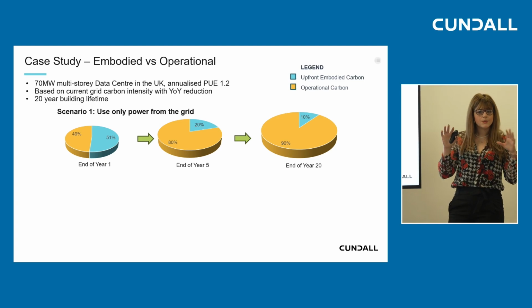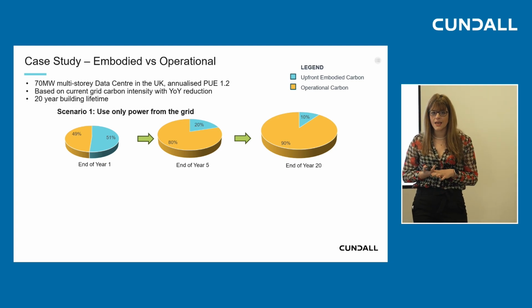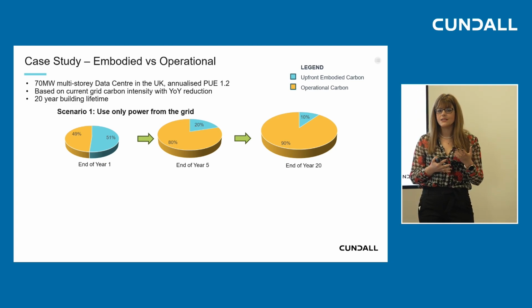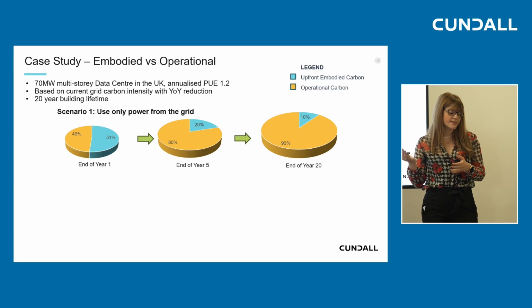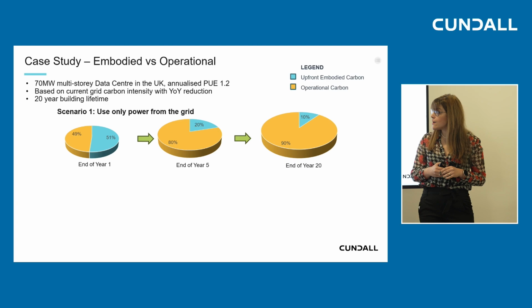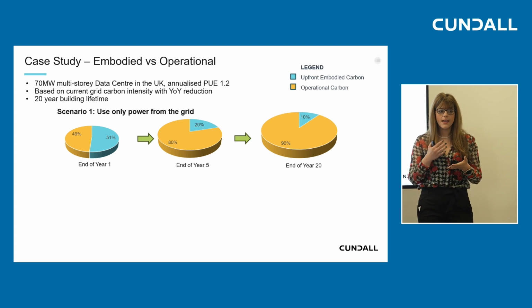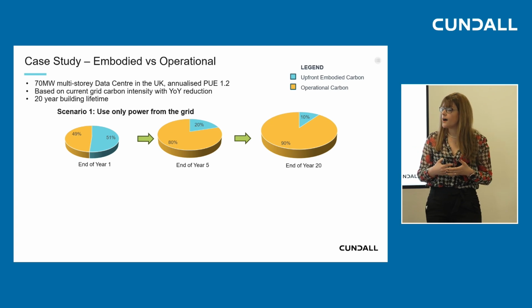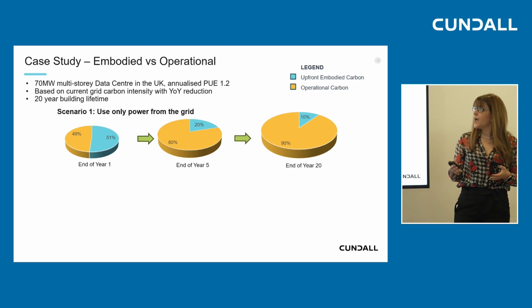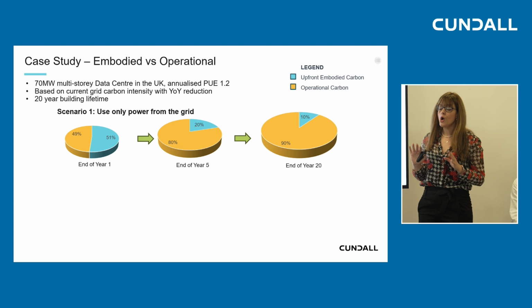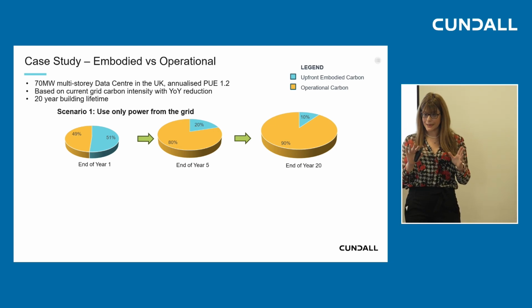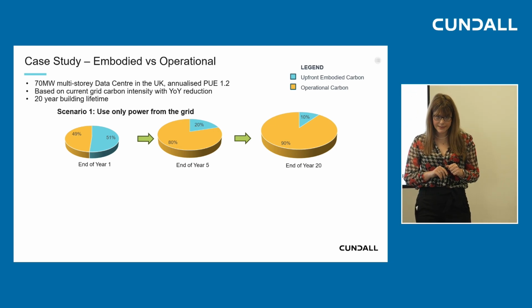Now, putting all the pieces of the puzzle together to understand the contribution of embodied carbon versus operational carbon in a data center building, we'll look at a case study. We've picked a 70 megawatt multi-story building in London, accounted for the carbon grid intensity of the UK to date, and applied a year-on-year reduction over the 20-year lifetime of the building. Note that for this example, we haven't accounted for any plant replacement over the 20-year building lifetime.